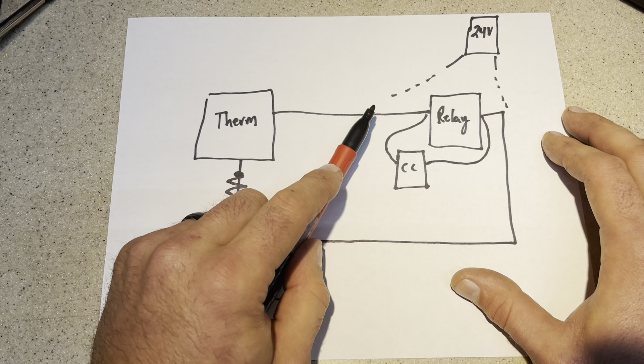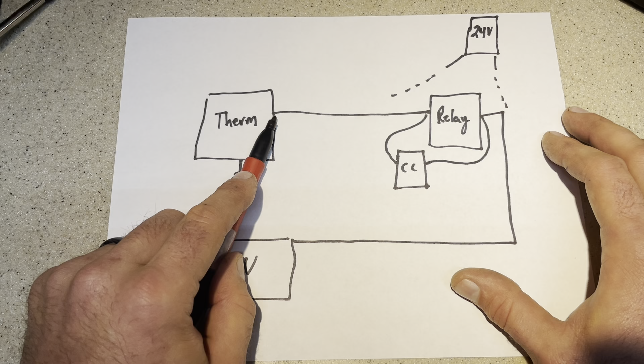So we measure here, keeping our black lead on common, and we take our red and measure: here, 0. We go to the thermostat, 0. 0, 24. 0, 24. So now we know our resistance is somewhere between this point and this point. There's some kind of high resistance in this thermostat wire that's going from the transformer to the thermostat.